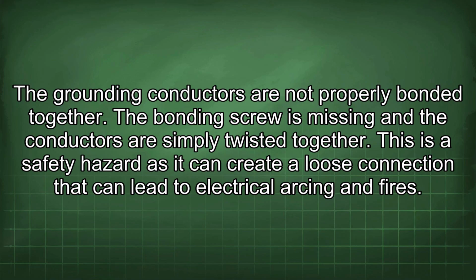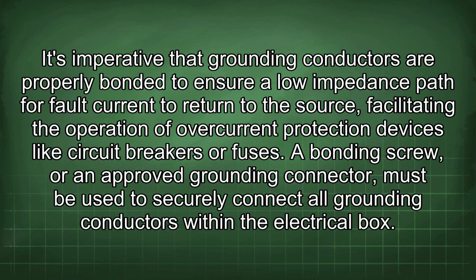Grounding conductors are not properly bonded together. The bonding screw is missing and the conductors are simply twisted together. This is a safety hazard as it can create a loose connection that can lead to electrical arcing and fires.